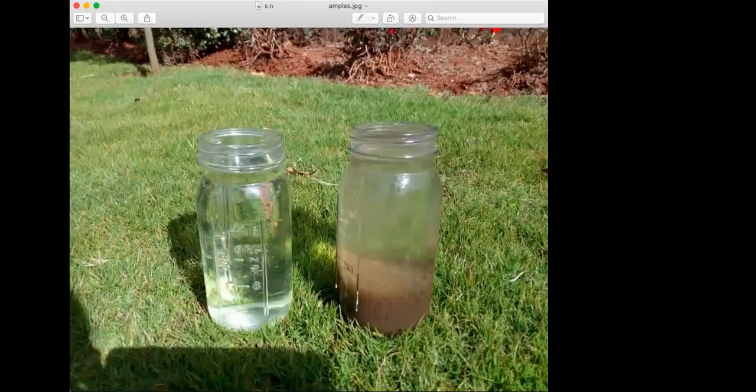Okay. Yeah, thank you very much. We always have polyaluminum chloride as an example pack, especially for these large scale systems. A lot of our clients have issues with power outages and they've not invested in backups. So as we are remedying a situation where maybe the SBR water is not coming out good, sometimes we will pour in the polyaluminum chloride, which acts as a very excellent flocculant, and it goes down just like this. This is pure biomass without any flocculants. But when you add a flocculant to a problematic system, it tends to behave exactly this way, and it settles very fast and you have your clear water.